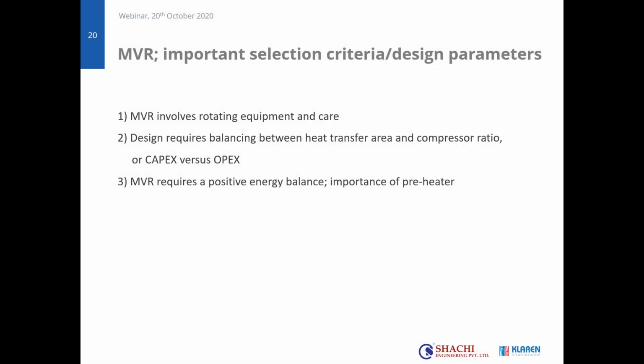So that is interesting. On the other hand, an MVR also requires care. And we know that in the market, there are quite some MVR units that have trouble, and some of them are not even used anymore. They have removed the compressor, or not removed it, but just bypassed it, and they run it on fresh steam, maybe in combination with a TVR.